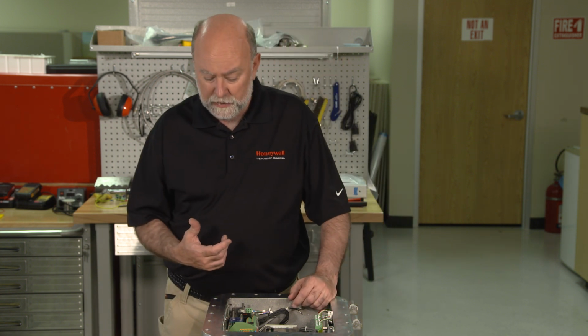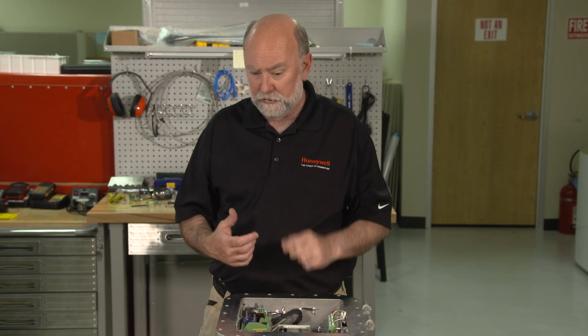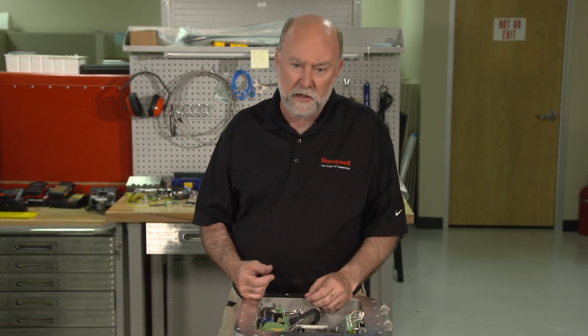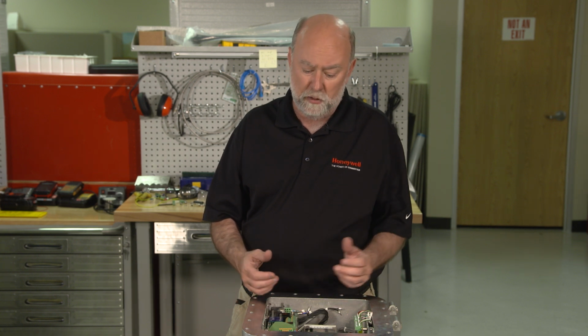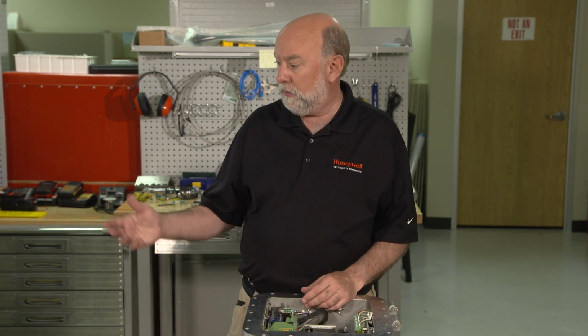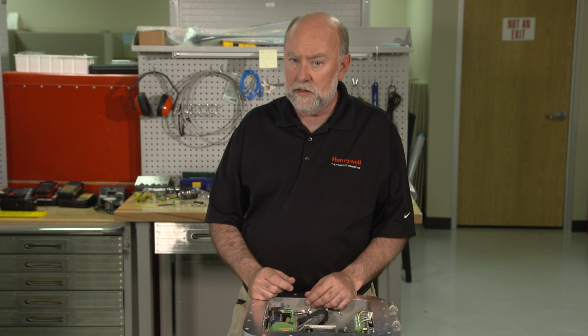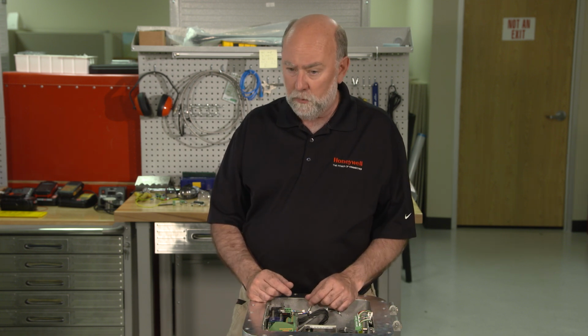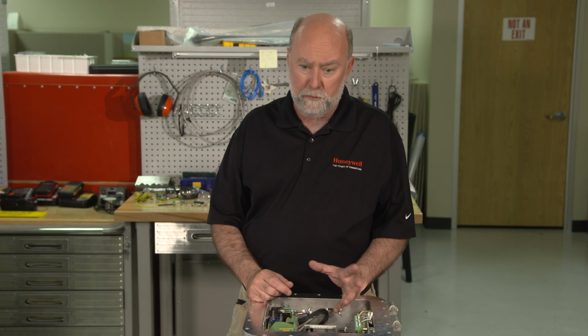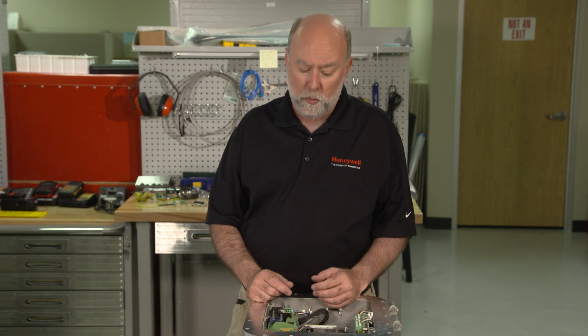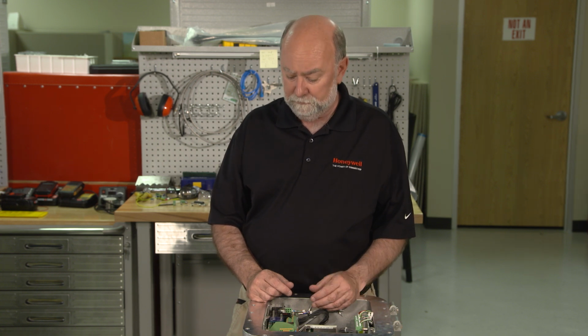Another possibility is that you use what's called a VDSL system. With that system, if you don't have any Cat5 or Cat6 cable pulled into your conduit, which you probably did not have with the Series 3 or Series 4 meters because there was no Ethernet connectivity with that hardware, then we have an option that may provide a good solution for that, which is to use a VDSL system.